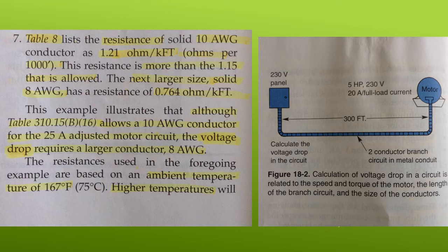The resistances used in the foregoing example are based on the ambient temperature of 167 degrees Fahrenheit, that is 75 degrees Celsius or centigrade. Higher temperatures will create higher conductor resistance and consequently higher voltage drops. See notes at the bottom of NEC Chapter 9, Table 8 to make any necessary adjustments.